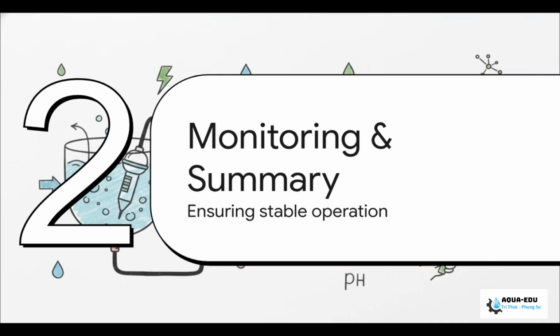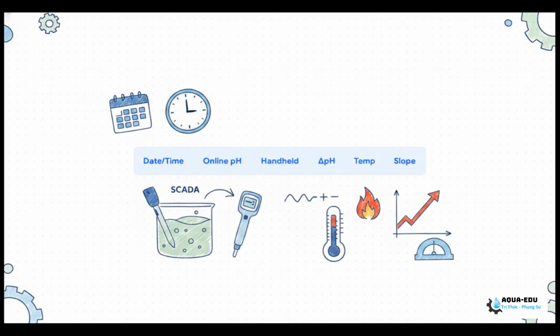And finally, Section 6, Monitoring and Summary. So, the fix is in place. Now what? Well, for the next 7 to 14 days, you are going to use this exact table format to rigorously log the system's performance. You'll record the date and time, the online SCADA pH, the handheld pH, and then calculate that deviation. You'll also log the temperature and the calibration slope. I know it sounds tedious, but this daily discipline is exactly what proves whether our fix is actually holding up under real, gritty plant conditions.